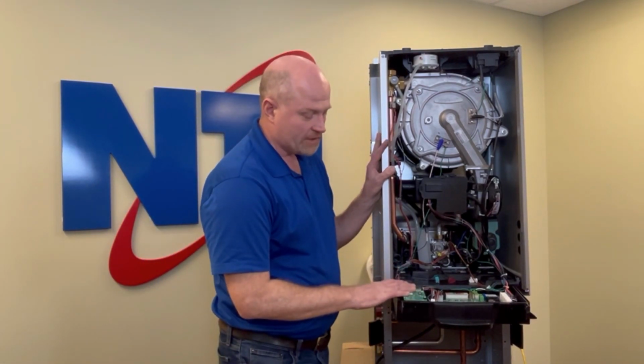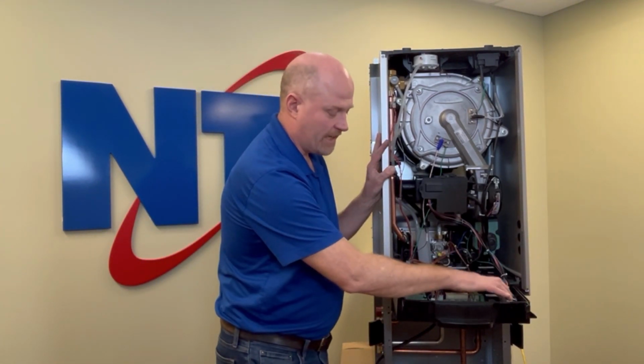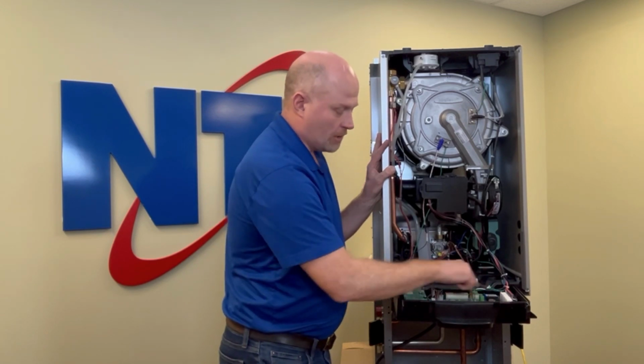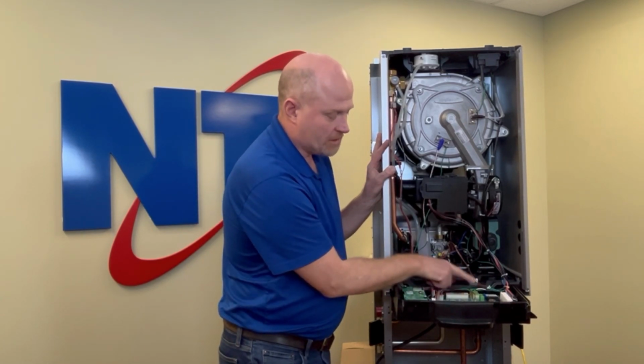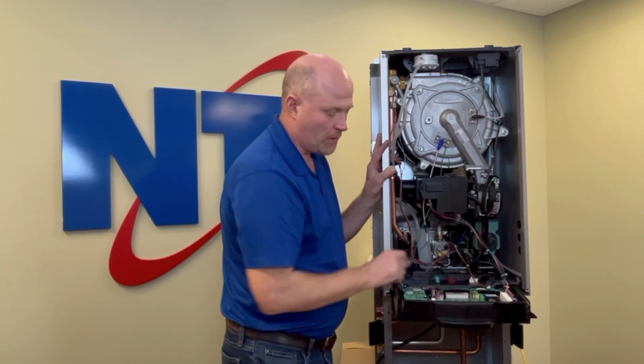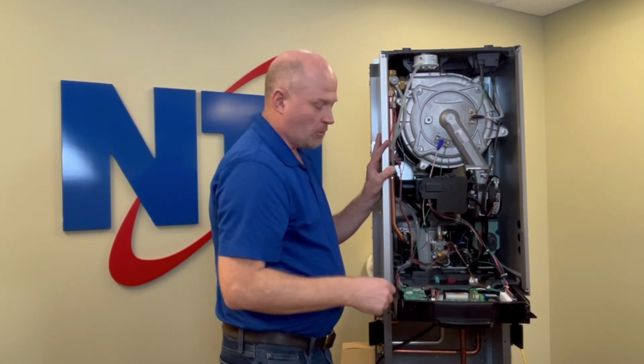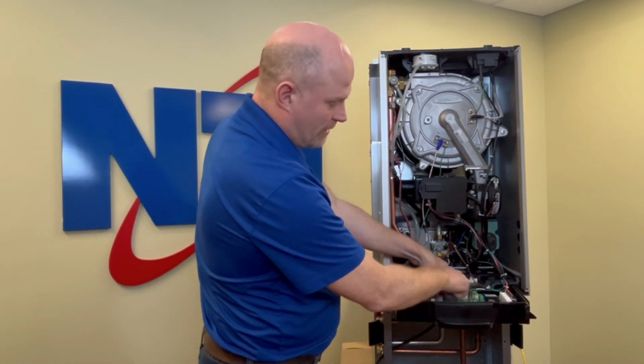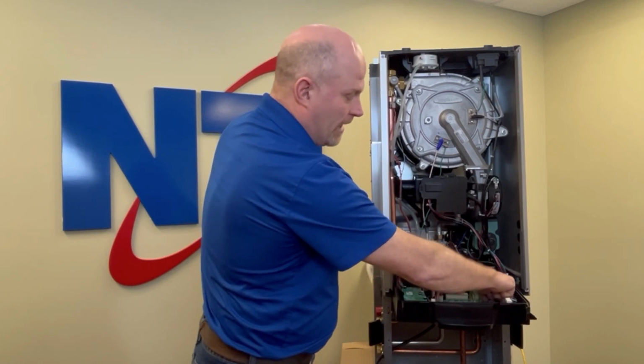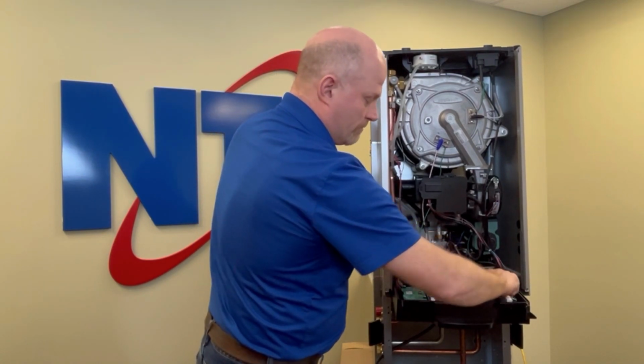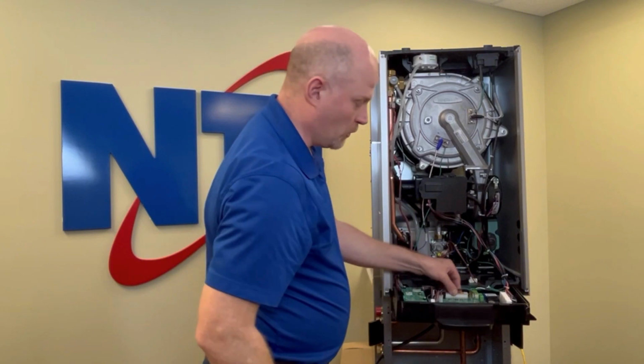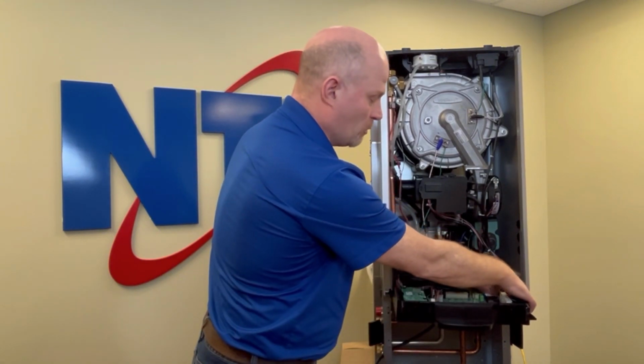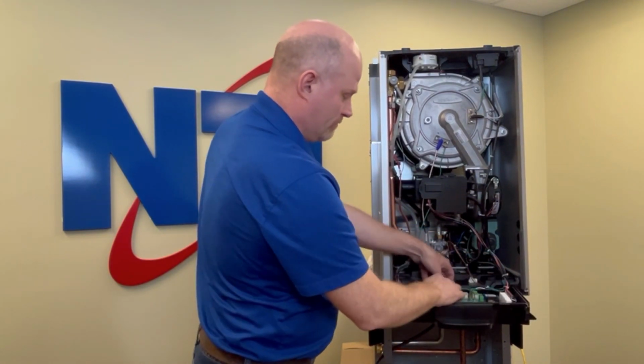If you have to replace the control board, simply disconnect all of the wires, including the 120 volt connection here, your flame probe, and your three grounds. All of these connectors will come off. There's two clips in the back of the circuit board that you push away. That lets you lift the circuit board up, and at that point you can lift it out of the boiler. Reinstall the new board in the opposite fashion.